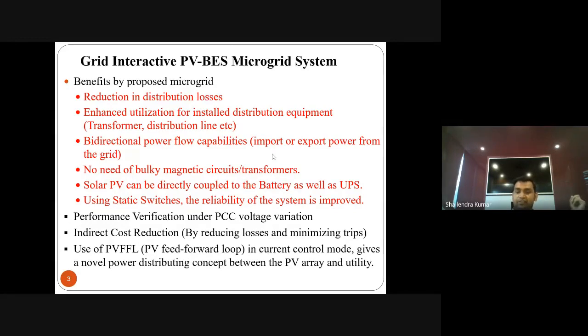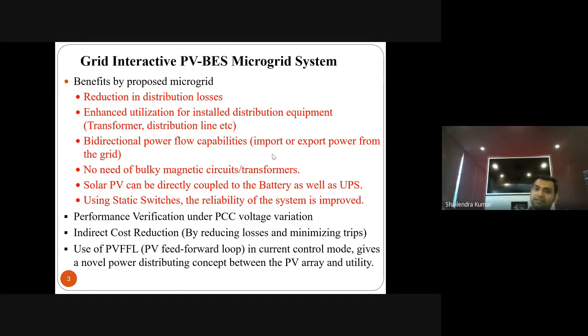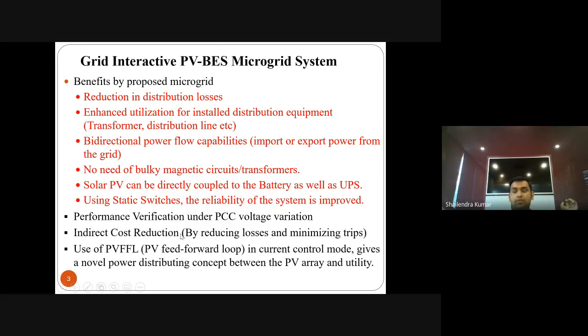On the control side, we use a PV feed-forward in the control loop. Using PV parameters and grid parameters, we design the feed-forward loop, which gives a power distribution concept. Because the utility grid already knows how much power is coming from the PV side, this reduces oscillations that would otherwise occur when suddenly injecting power to the utility grid.